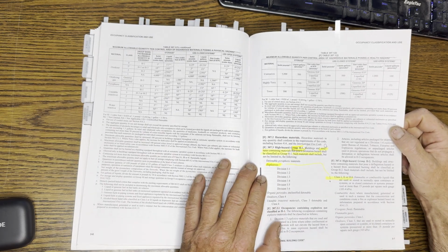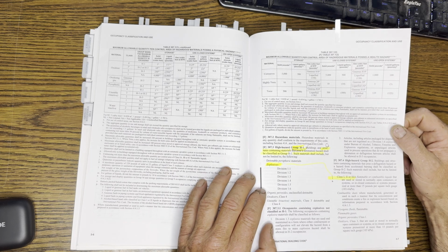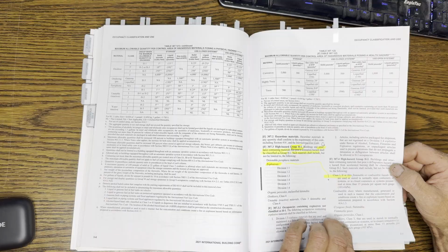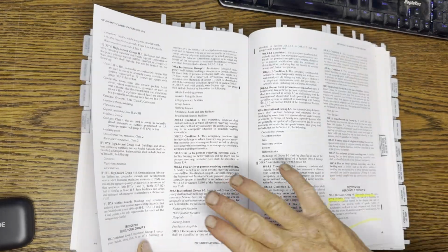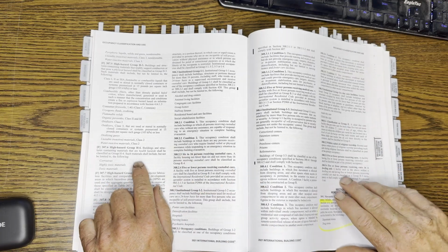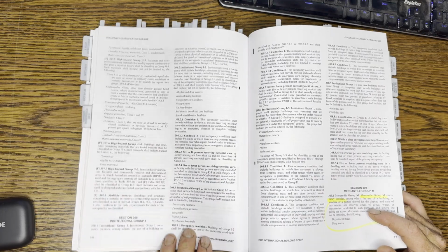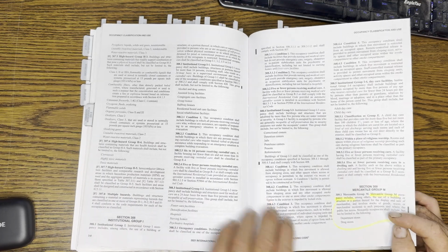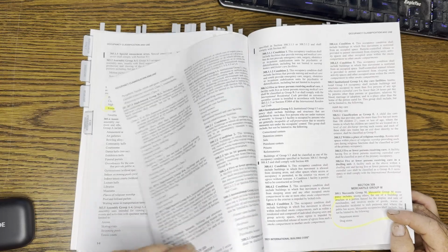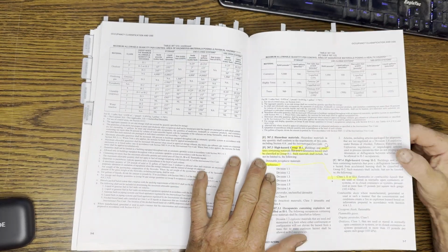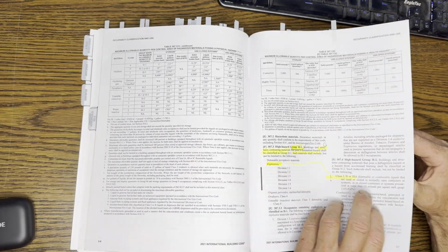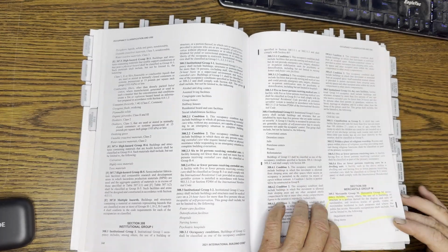As far as Group H, just be aware you have 5 H occupancies. One is explosives, one's gases, one's vapors, one's dusts. And then you drop down to toxic materials. And then H5 would be a semiconductor type thing. So it's worthwhile to know, if you have a question like explosive storage above the maximum allowable quantities permitted by Chapter 50 of the International Fire Code, what occupancy? It's H1. That's how they define that.